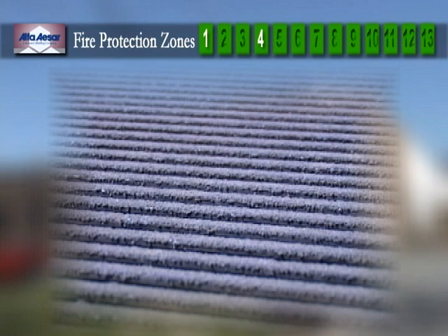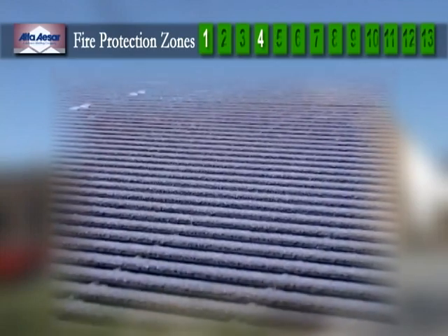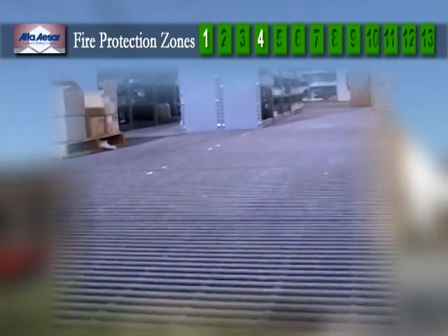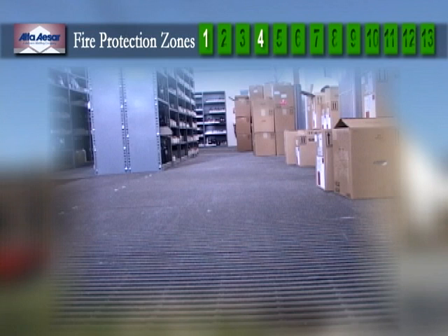The lowest level of storage in the rack system is a fiberglass plastic-coated material that forms an open grate floor through which any spilled liquids will fall in the event that the integrity of a container is compromised. The coated nature of the surface is intended to mitigate the formation of sparks. A concrete floor is located approximately 36 inches below the open grate floor to capture spilled liquids and any release of the AFFF extinguishing system.